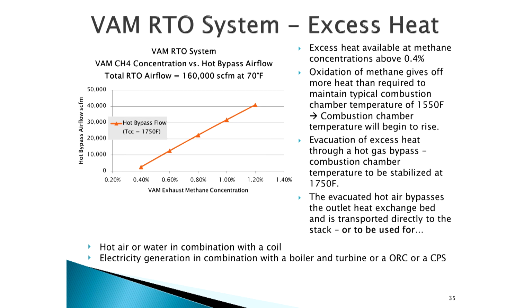So we evacuate the extra heat through that hot bypass damper I talked about, and we can transport it directly out of the stack, or we can use hot air or water in combination with the secondary heat recovery coil, or we can run a steam turbine, boiler, or many different technologies we can deploy to use that heat.